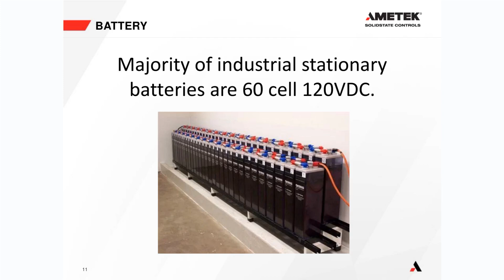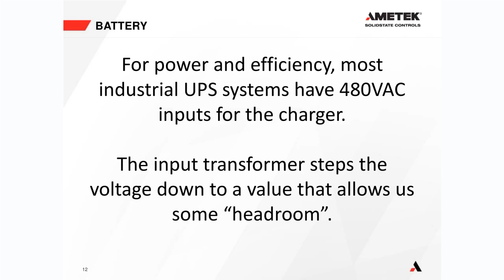Now there are two main reasons to have an isolation transformer on the input to your UPS. I've mentioned one of them before. The majority of industrial stationary batteries are 60 cell, 120 volt DC nominal, so we have to be able to charge those batteries. For power and efficiency, most industrial UPS manufacturers use 480 volts three-phase inputs from the MCC to their charger. It just makes more sense. So the input transformer steps the voltage down to a value that allows us to charge the batteries with a little bit of wiggle room. We call it headroom.